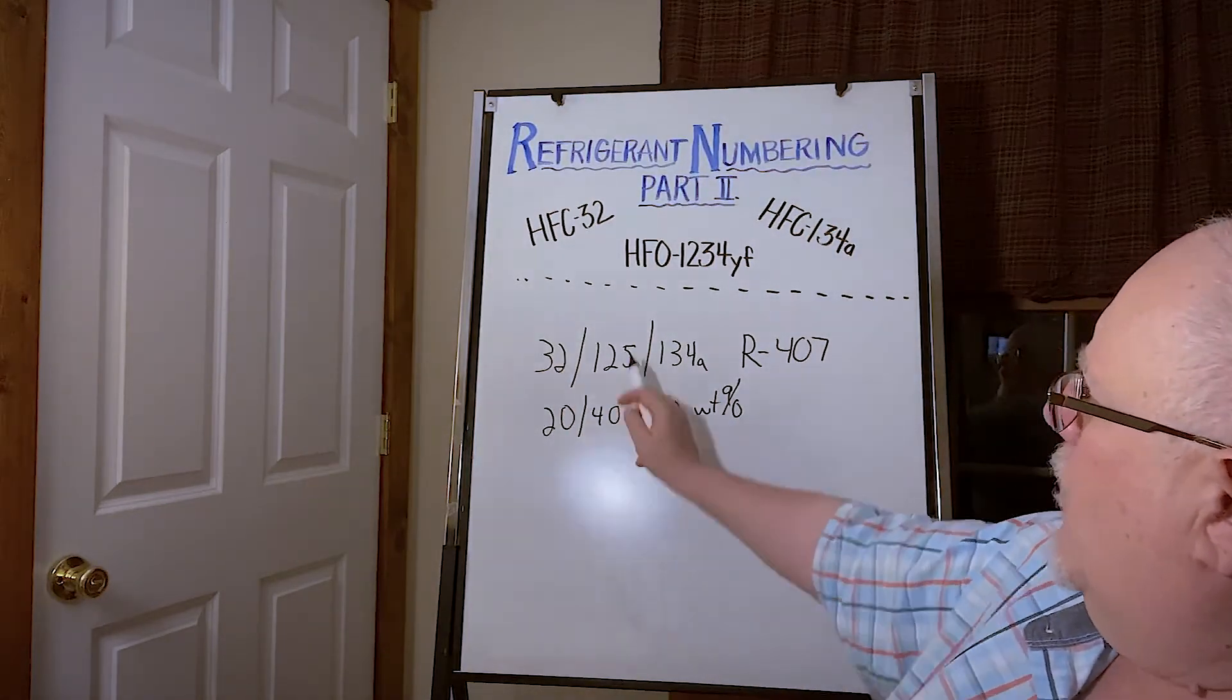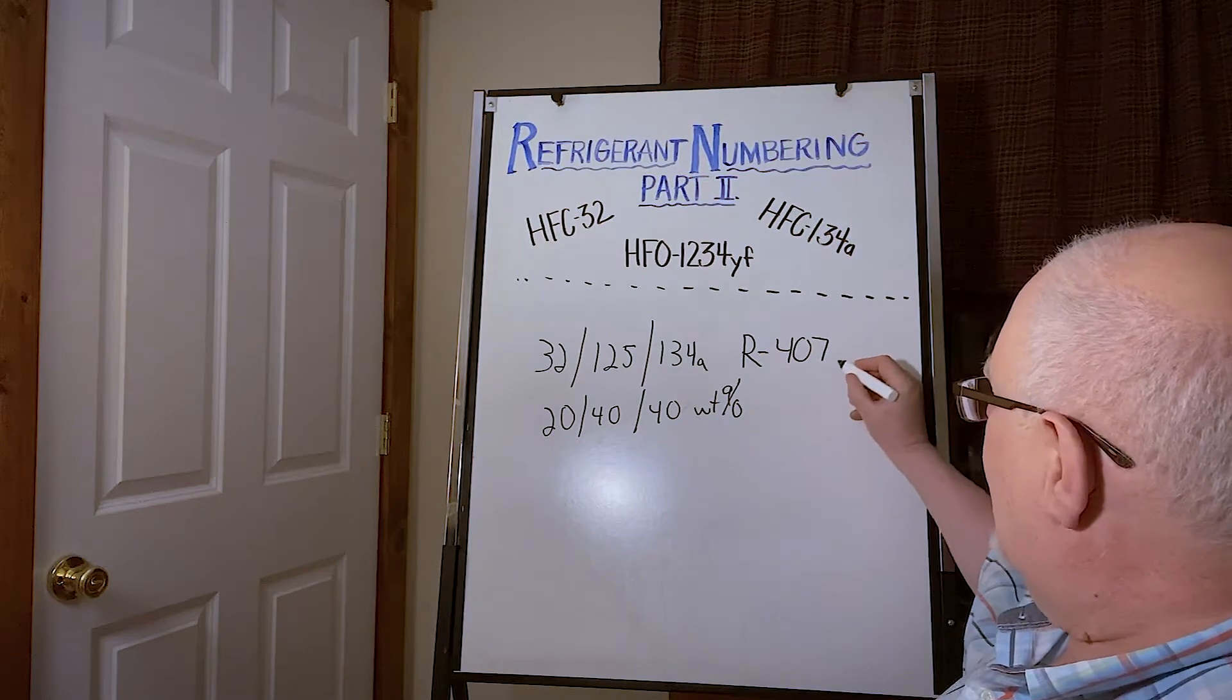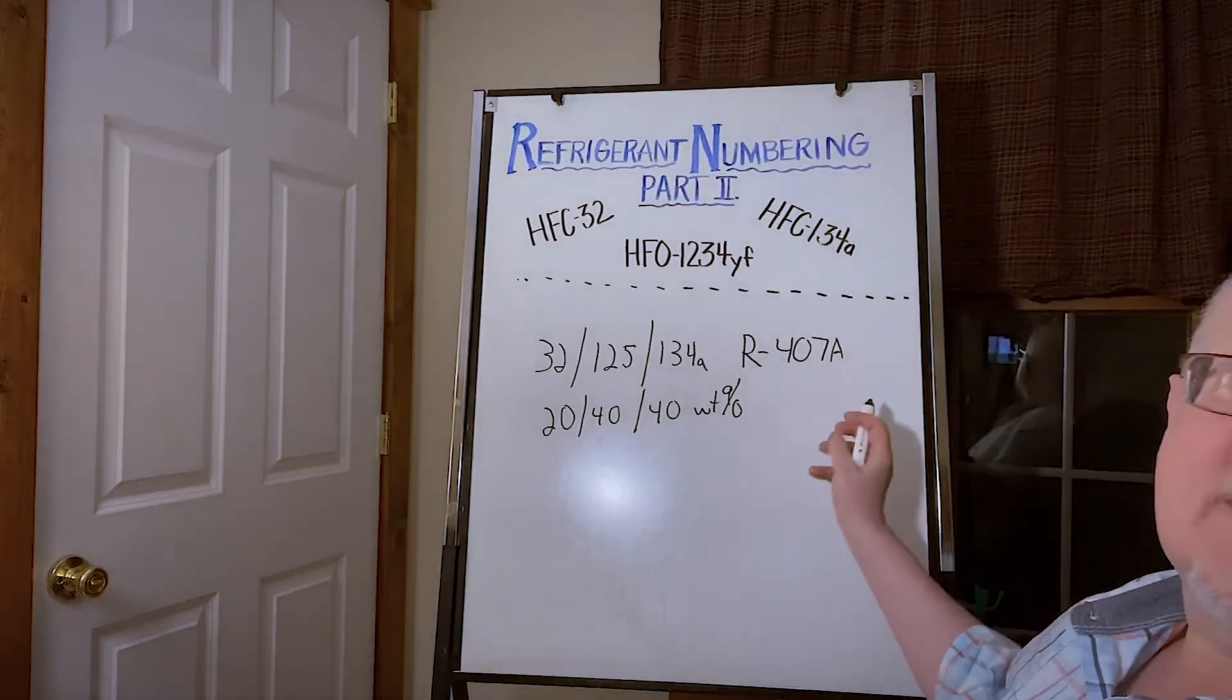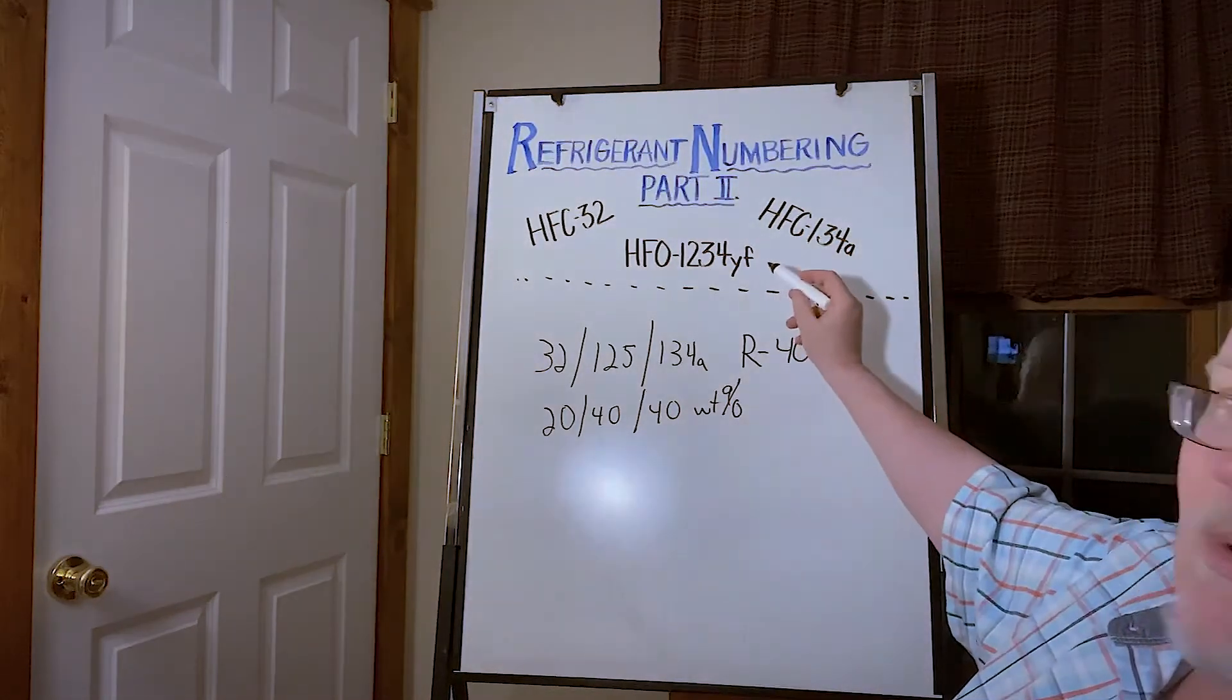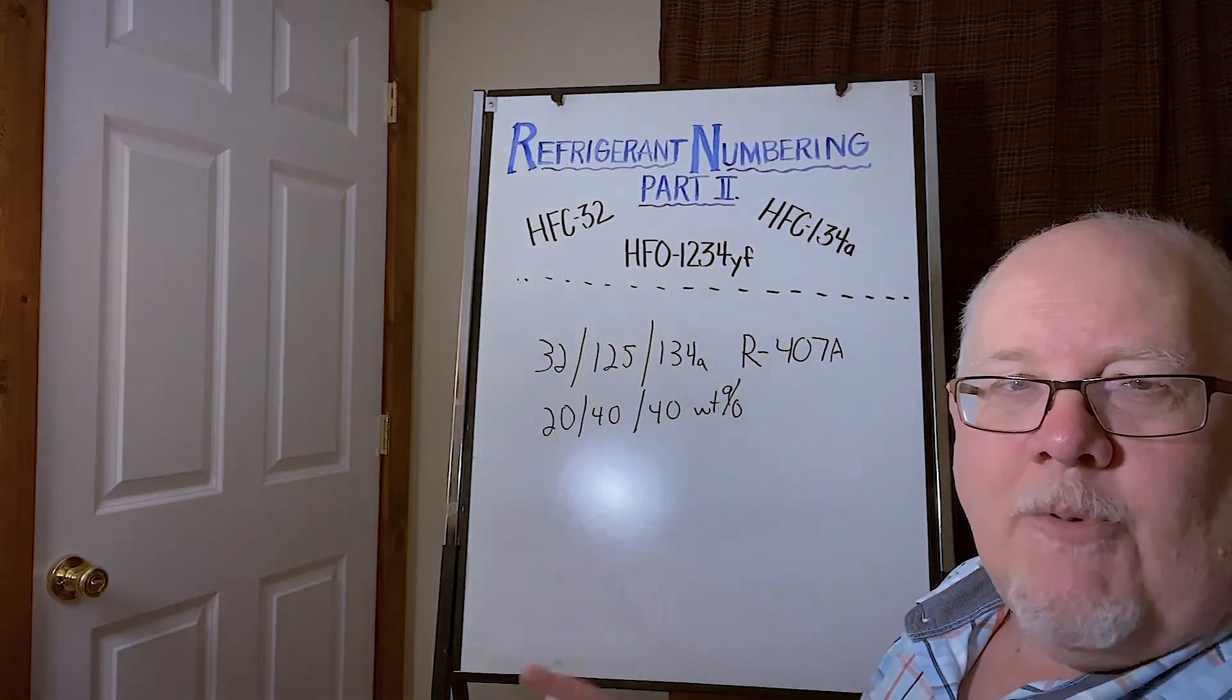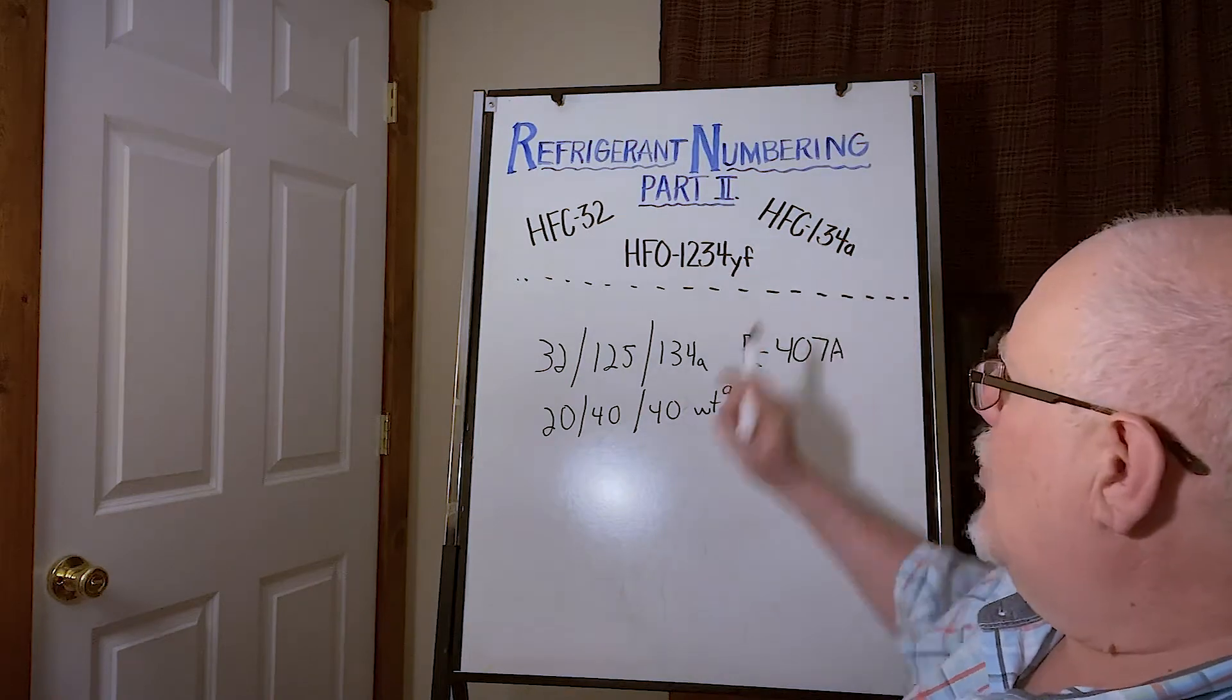20% HFC-32, 40% HFC-125, 40% HFC-134A. And that got the designation 407A. Notice this is a capital A, different than the small a or the small YF we see in individual things. Important distinction. Uppercase letters designate blends. These are more for the molecules.